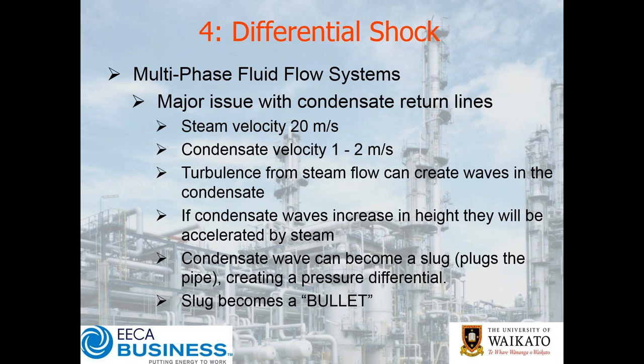Some of you might have a plant that was designed at a certain nameplate, and then everyone's trying to get the hidden plant, running at 120% of nameplate. Of course, what happens when we do that is all of our steam is up at 120%, which means our condensate is up at 120%, which means our condensate velocities and our flash steam velocities are all that much higher — and this is where things start to tip over into becoming an issue.